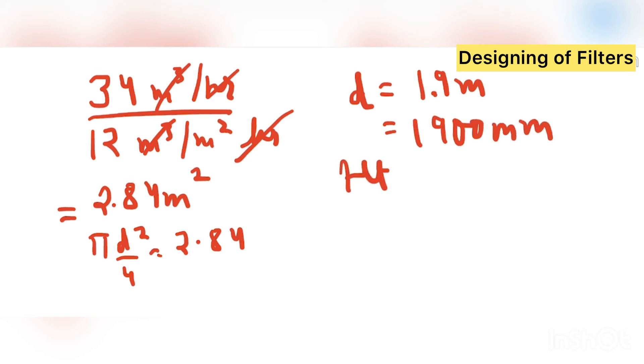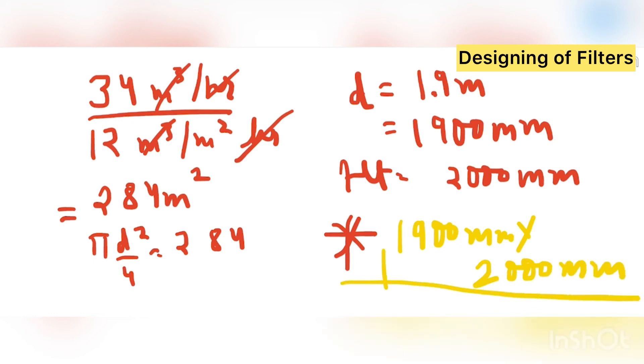And height, as I told you, is 2000 mm. So the total dimension what I am getting is 1900 mm by 2000 mm is the diameter and height of filter. So in the same way, dimension of MGF and dimension of dual media filter can be calculated in the same manner.